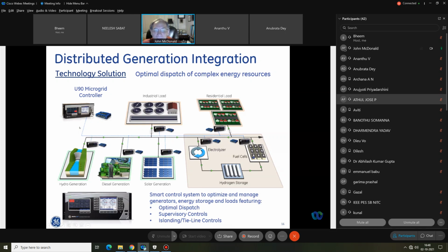So we took a microprocessor-based protective relay, with GE this was the U90 relay, and we added logic to the relay to become the microgrid controller. And then you can see that throughout the microgrid, we have blue boxes, which are high-speed communications equipment. So every 2 seconds, we know exactly what's happening, and we're optimizing the operation of the microgrid. Okay.